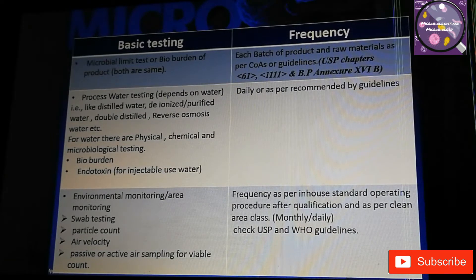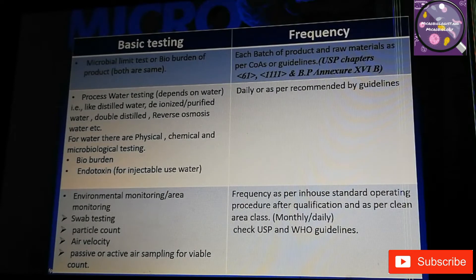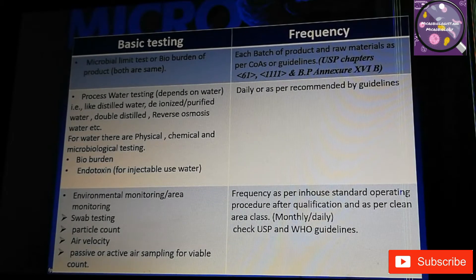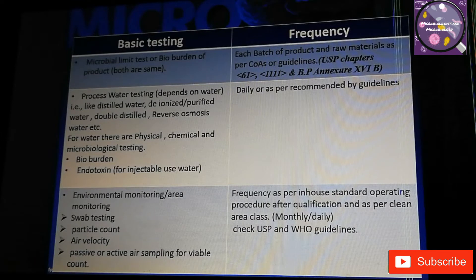Another test is environmental monitoring or area monitoring. This kind of monitoring is very important for clean rooms and controlled environments. It includes swab testing, particle count, air velocity, passive or active air sampling for viable count, and also personal hygiene testing such as glove testing and gown testing.